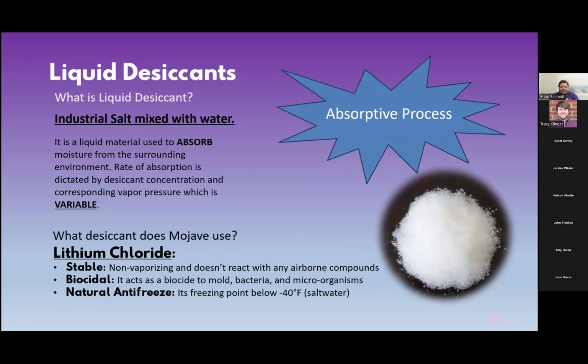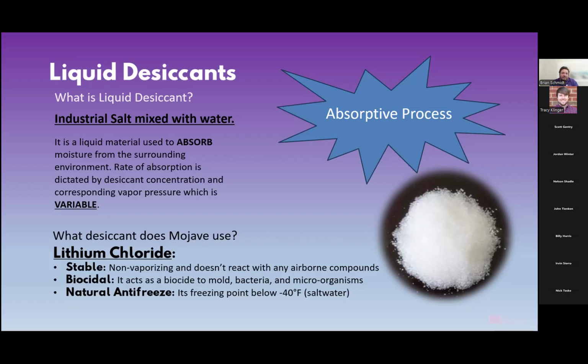So, on the subject of liquid desiccants, what exactly is it? Well, it's just an industrial salt mixed with water, right? So we have different concentrations. Again, the more concentrated, the lower the vapor pressure. The lower the vapor pressure, the more affinity it has for absorbing moisture. So it is a liquid material used to absorb, not adsorb, absorb moisture from the surrounding environment. The rate of absorption is dictated by desiccant concentration and corresponding vapor pressure, which is variable. So again, as I mentioned in that previous slide, we have independent temperature and humidity control. We are manipulating the concentration of the desiccant, again, using how much heat we allow to evaporate moisture from the desiccant. So we are manipulating that, causing it to be variable, causing our vapor pressure to be variable.